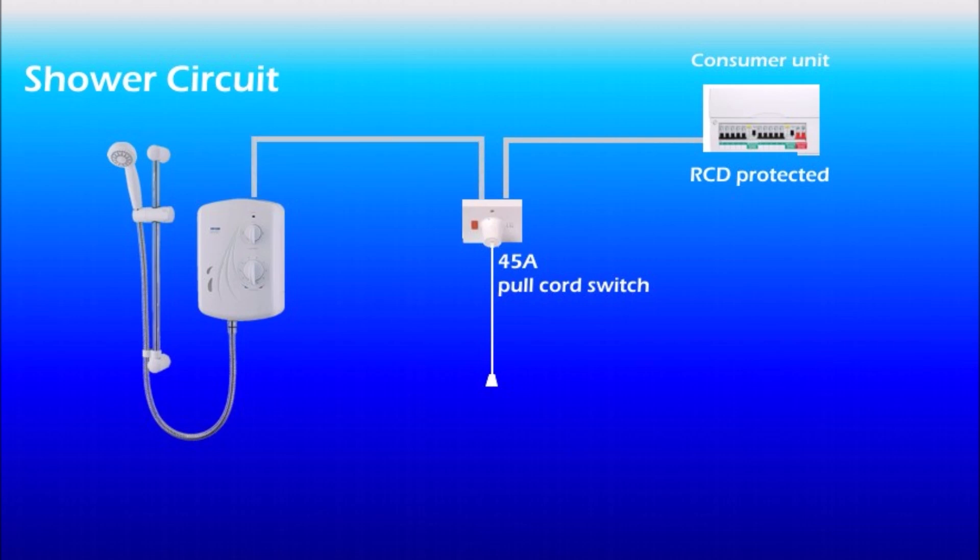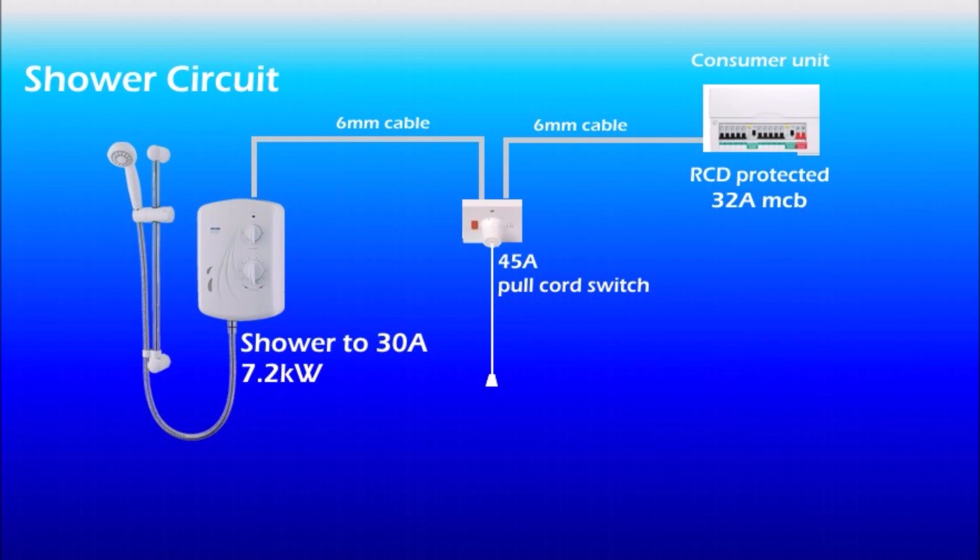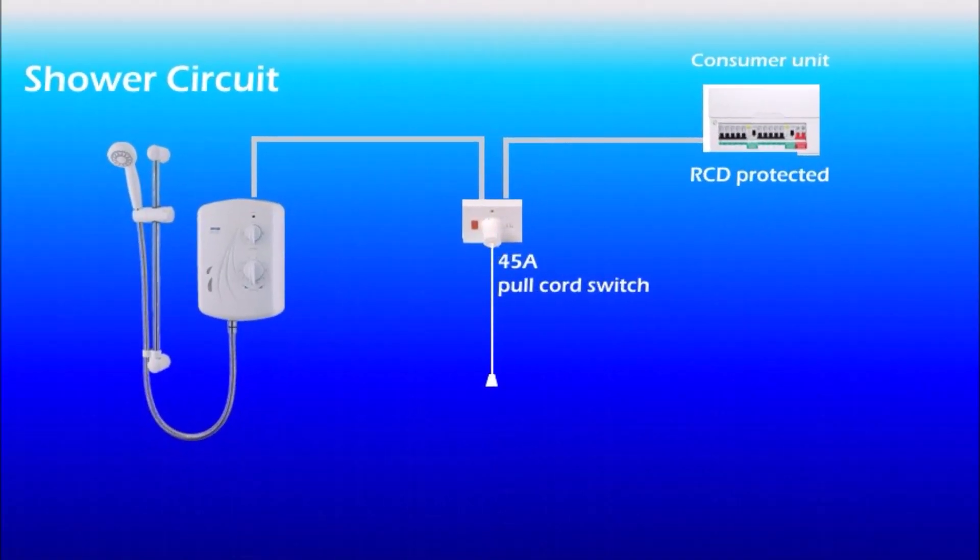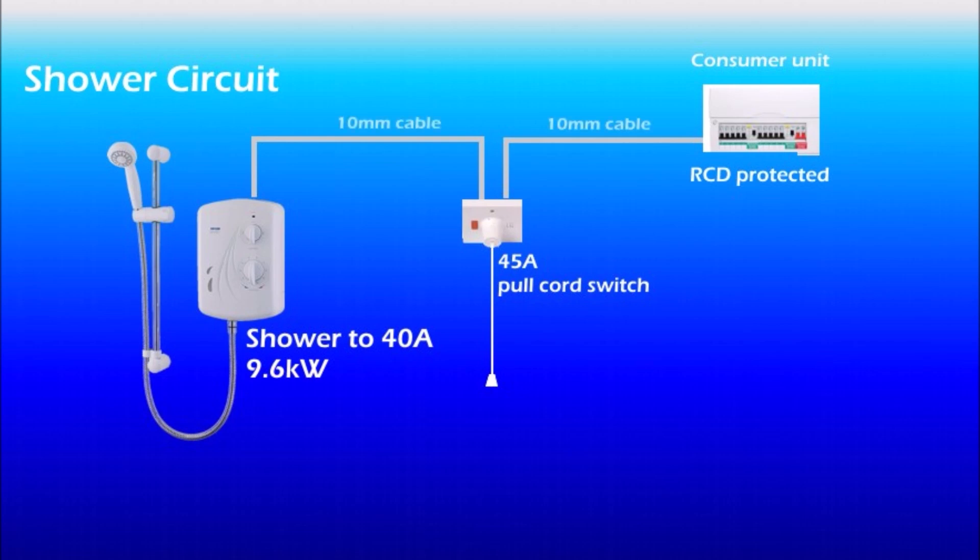And from the switch we need to run cable straight to the electric shower. And now size of the cable and rating of the MCB depends on the rating of the shower unit. If the shower unit rating is up to 30 amp that is 7.2 kW then you need to use a 6mm cable and 32 amp MCB. But if the shower is 40 amp then you should run 10mm cable and install 40 amp MCB.